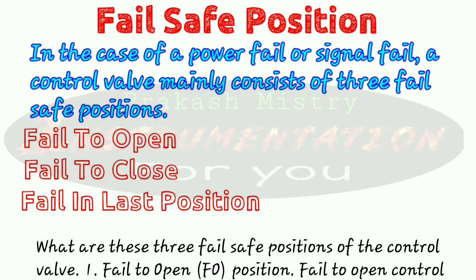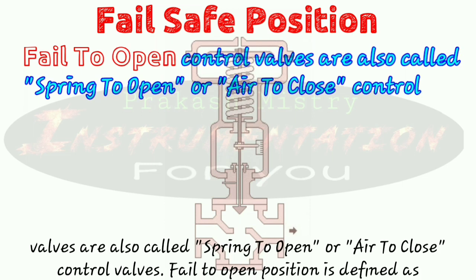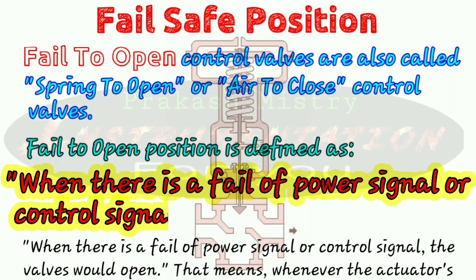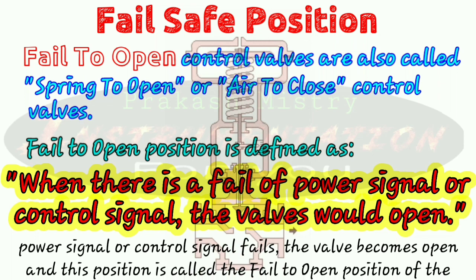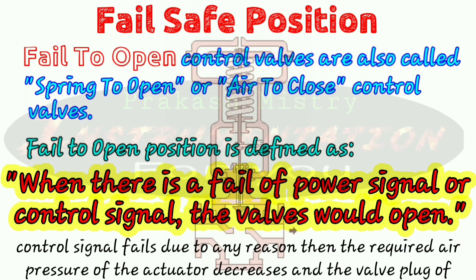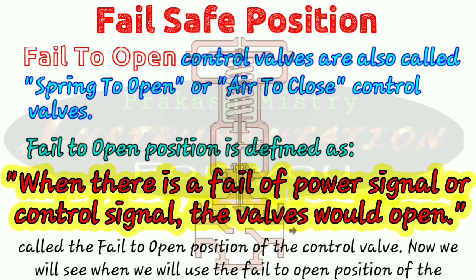The first fail-safe position is fail to open. Fail to open control valves are also called spring-to-open or air-to-close control valves. Fail to open position is defined as when there is a failure of the power signal or control signal, the valve would open. Whenever the actuator's power signal or control signal fails, the valve becomes open, and this position is called the fail to open position. Such control valves require air pressure to keep the valve closed. When the power or control signal fails, the required air pressure decreases and the valve plug moves toward the open position due to the actuator spring.